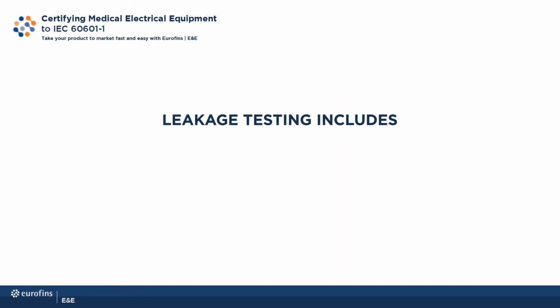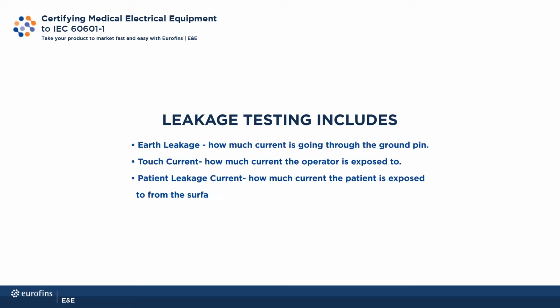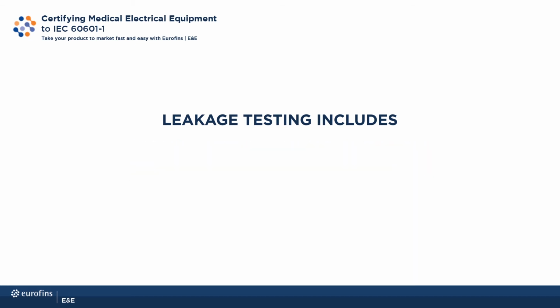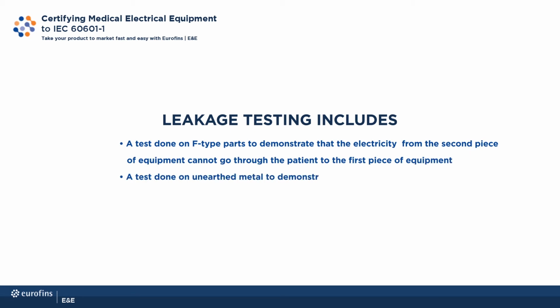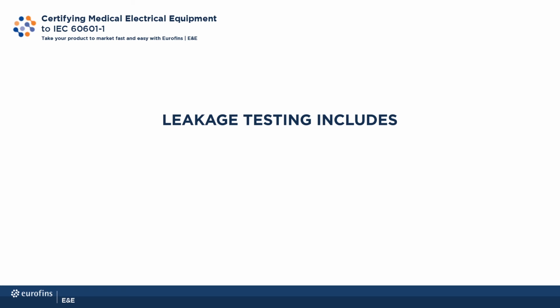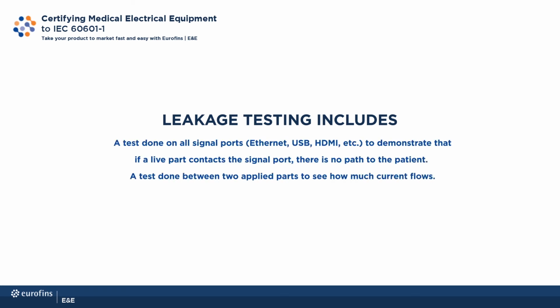First, we measure the leakage that goes through the ground pin and the leakage that is on the surface of the equipment or applied part that doesn't go into the ground pin. Then we measure leakage that may come from other pieces of equipment that we can't control, and we cover leakage from metal that has no path to ground. Finally, we measure leakage from signal ports that can't be controlled, the cumulative effects of leakage from several points, and from point to point when more than one part of the equipment touches the patient. And there are some tests that are new and specific to medical electrical equipment, making sure that rolling equipment does not tip over or stop functioning.